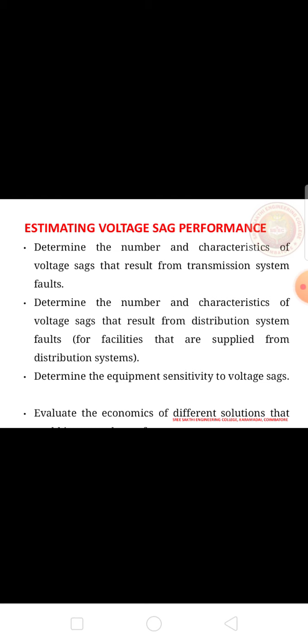The following procedures apply when working with industrial customers to assure compatibility between the supply system characteristics and the facility operation. First, determine the number and characteristics of voltage sags that result from transmission system faults. Second, distribution system faults. Third, equipment sensitivity to voltage sag. And fourth, different solutions that could improve the performance either on the supply system or within the customer facilities. So, that is estimating voltage sag performance.